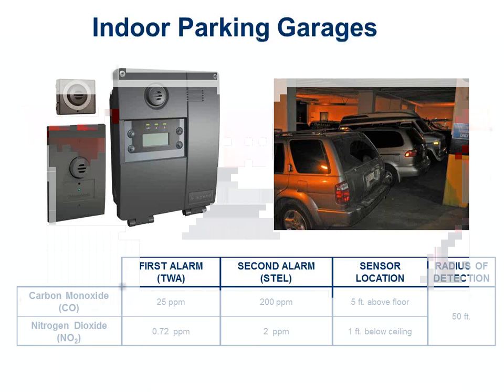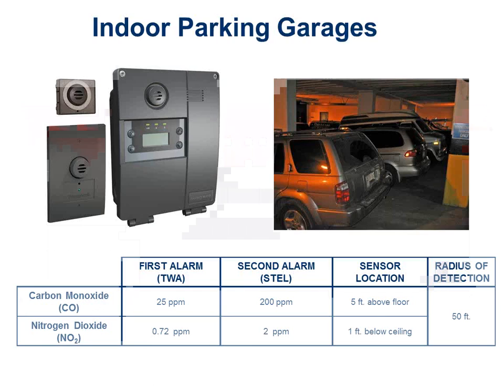Right? Nitrogen dioxide, if I have diesel vehicles, the thresholds are much, much lower. 0.7 parts per million is typically my control point. I want to keep it below that, so I will turn exhaust fans on to maintain something less than 0.7. And if I get to 2 parts per million, I will alarm it and tell you to get out of the building. I typically measure that below the ceiling in terms of a vehicle scenario for nitrogen dioxide, because when it's hot, like it's coming out of the exhaust stack of your truck at 1500 degrees, it's going to be very hot. It's going to rise up towards the ceiling. So I'm going to measure it up there. And both these sensor types typically handle a 50-foot radius of detection.